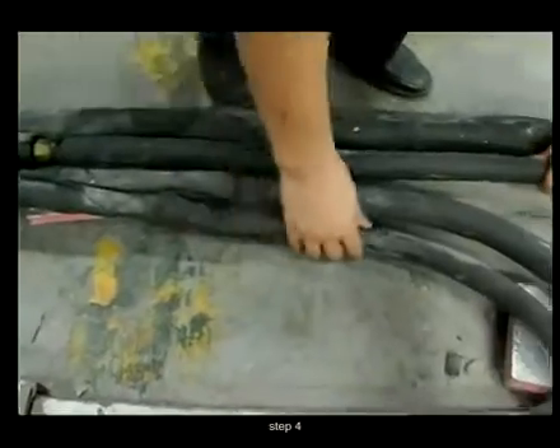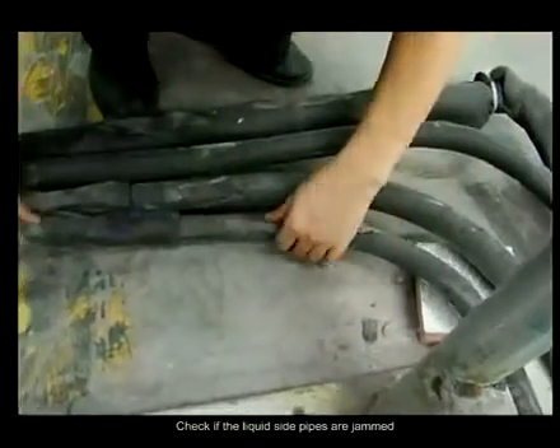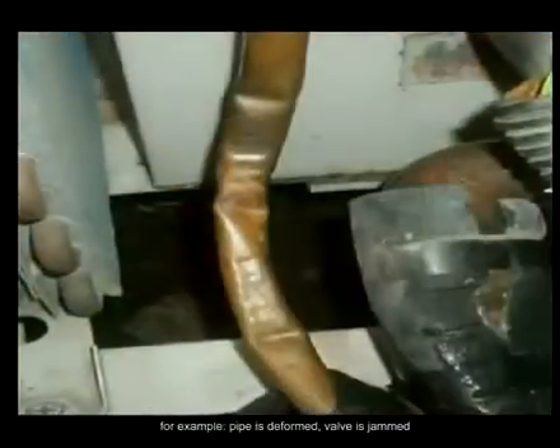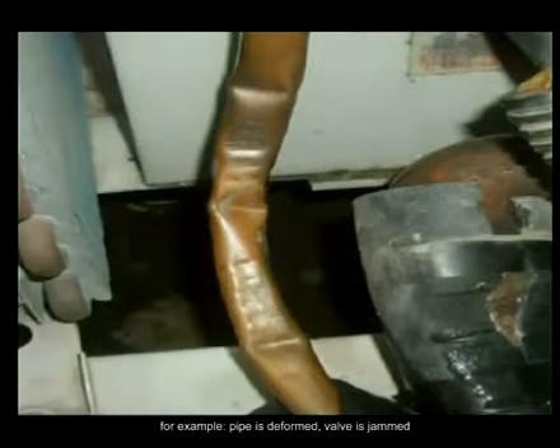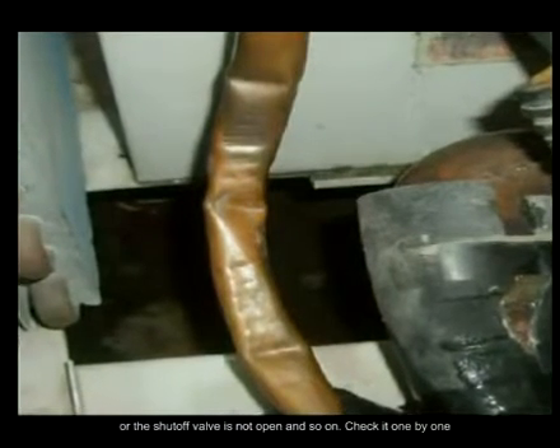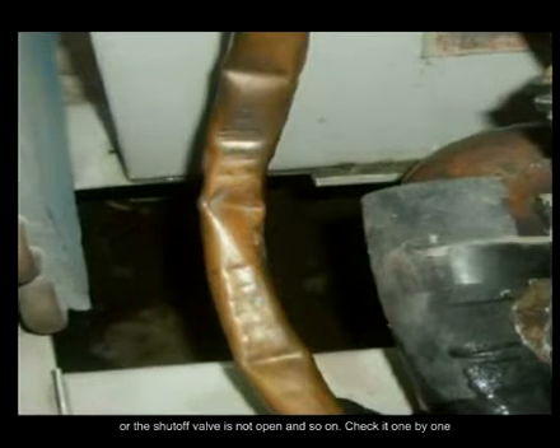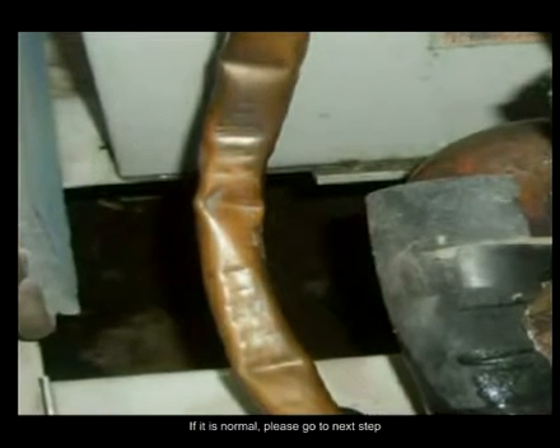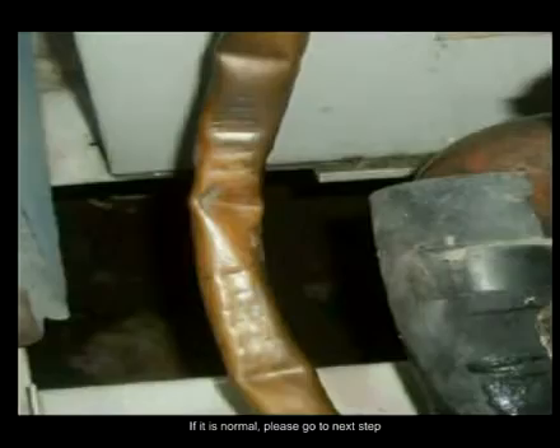Step 4. Check if the liquid side pipes are jammed. For example, the pipe is deformed, a valve is jammed, or the shutoff valve is not open, and so on. Check it one by one. If it is normal, please go to the next step.